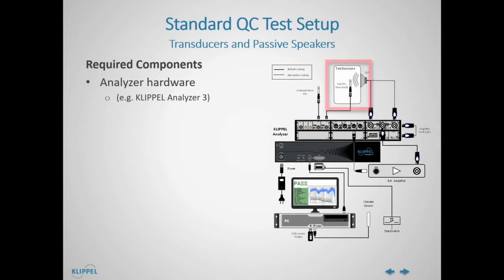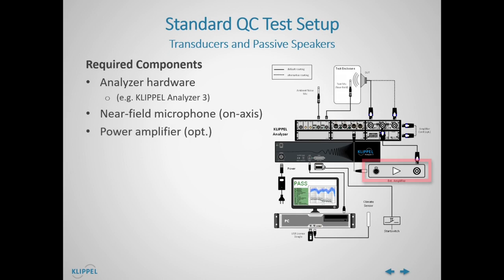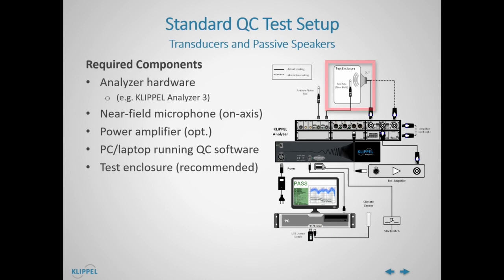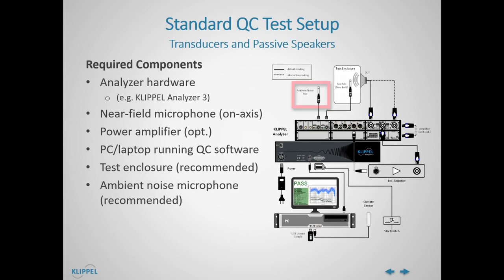We need at least one test microphone in the DUT's near field. An external power amplifier can be added in case the power or peak voltage provided by the internal amplifier of the analyzer is insufficient. A Windows PC with the Klippel QC software is connected to the analyzer. An optional test enclosure is highly recommended for ambient noise attenuation and defined test conditions. Additional robustness is obtained by adding an ambient noise microphone.